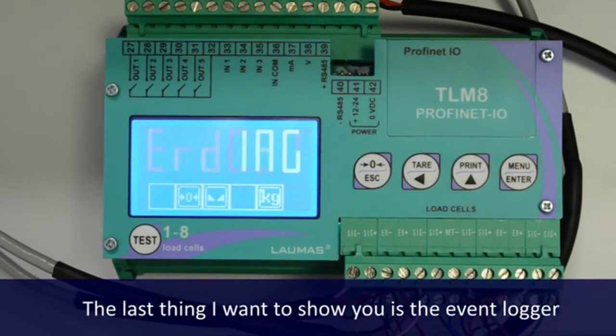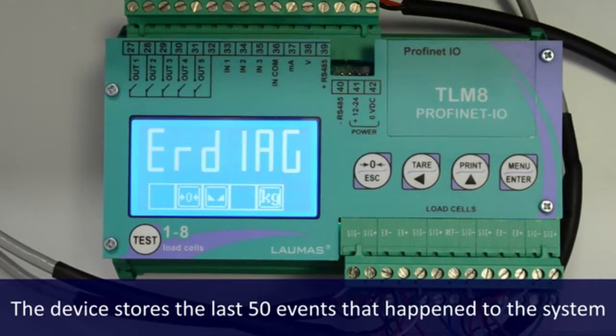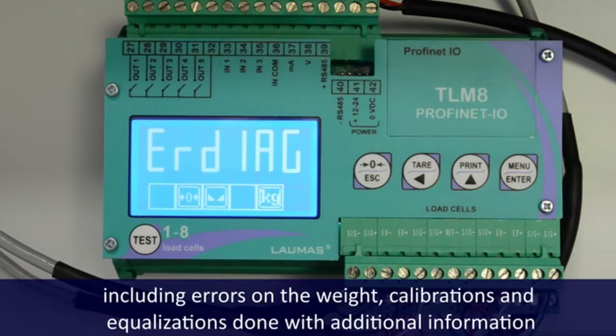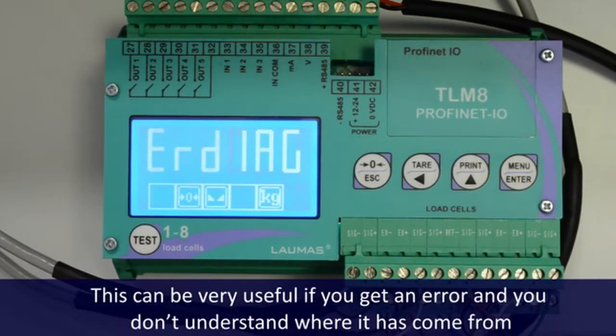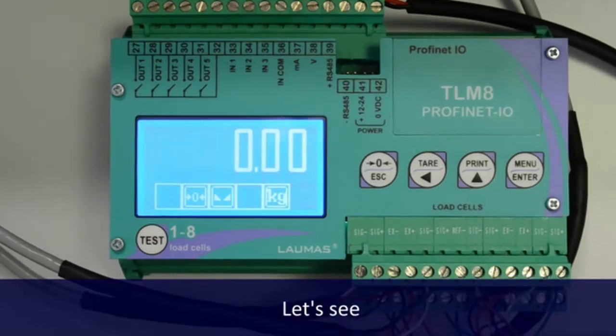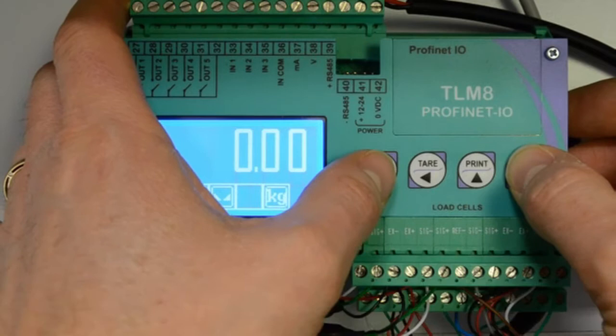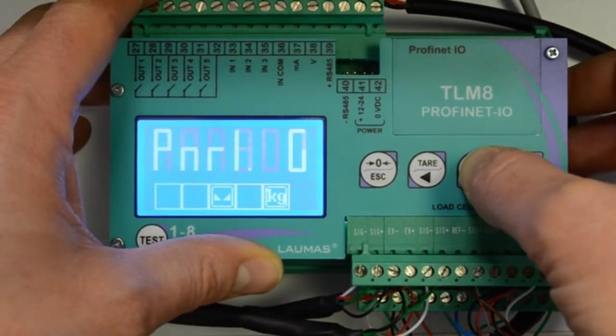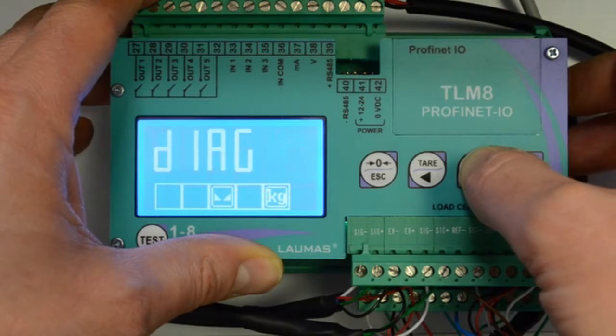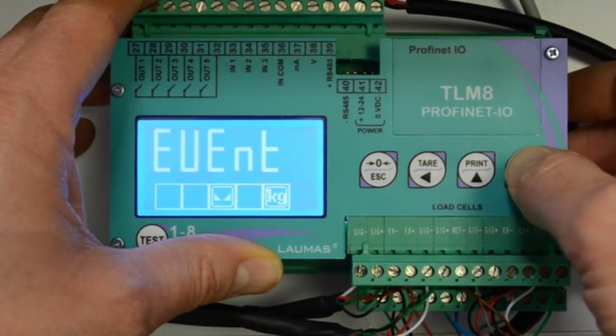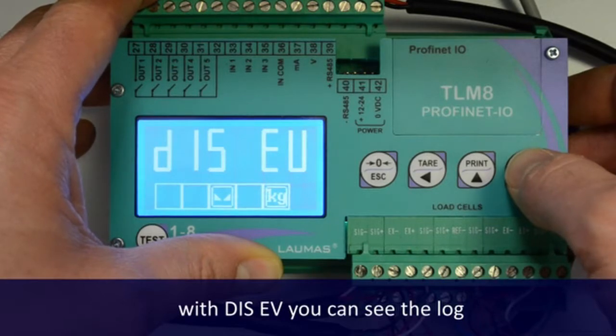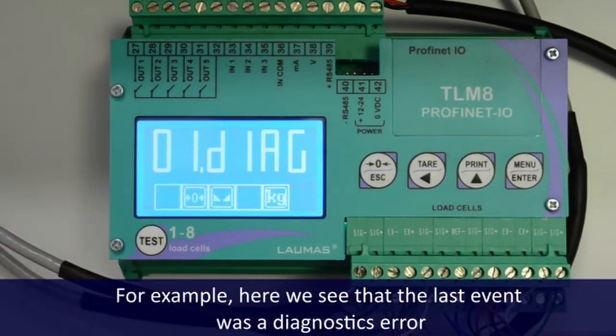The last thing I want to show you is the event logger. The device stores the last 50 events that happened to the system, including errors on the weight, calibration and equalizations done, with additional information. This can be very useful if you get an error and you don't understand where it has come from. Let's see. There is a menu item called Event. And with this EV, you can see the log. For example, here we see that the last event was a diagnostics error.